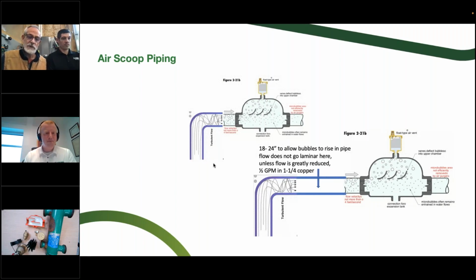Yeah, we don't want those air bubbles in our pump. We certainly don't want them in a little high efficiency boiler. We're going to overheat the metal of the boiler. And you don't want them in your radiators or your fin tube or your radiant tubing, whatever it might be. We want water touching all the surfaces, not little micro bubbles, because you reduce your heat transfer if you've got air of any type in your system, in your pipes and your radiators.